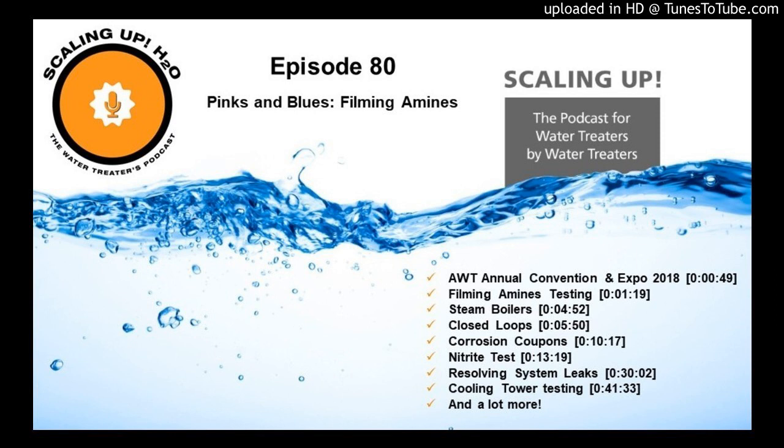And the way you want to do this is you want to dissolve that sodium nitrite. So that way you don't have to worry about crystals floating somewhere and not dissolving or getting to the bottom of the pot feeder or clogging up a line or something like that. Just dissolve it. It totally takes any issues out of the equation with dissolving. Then you would put that 1 pound that you have dissolved into the pot feeder. You will let that circulate.